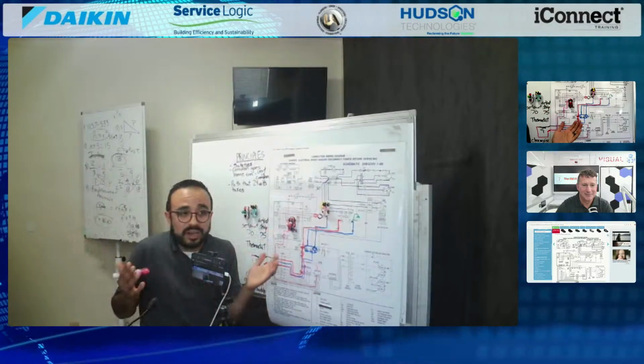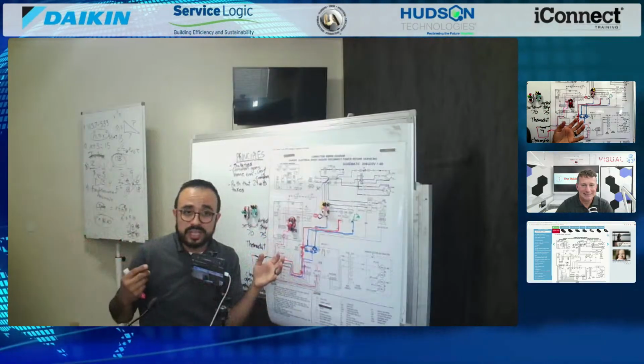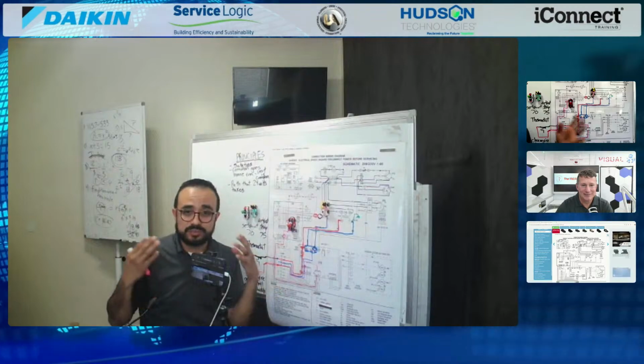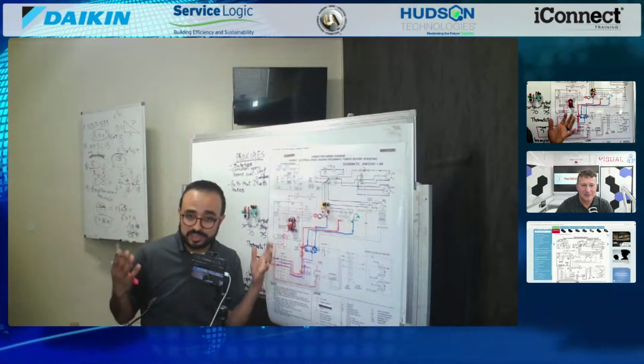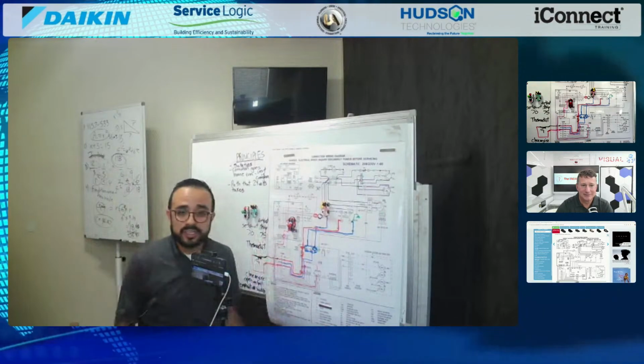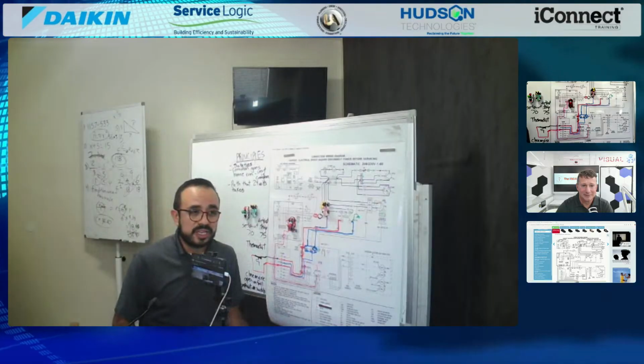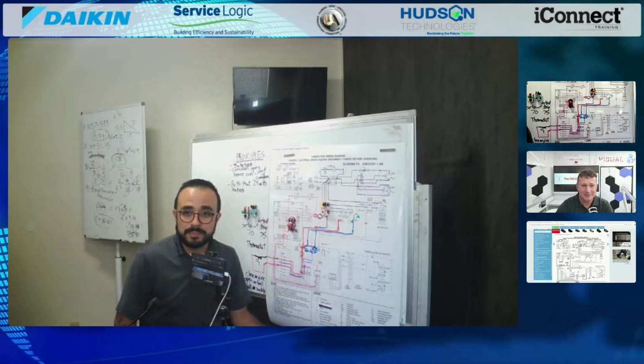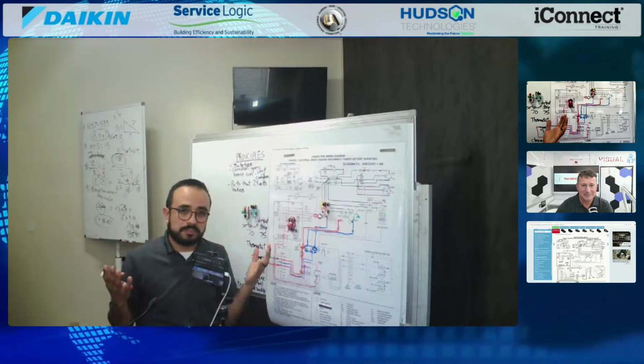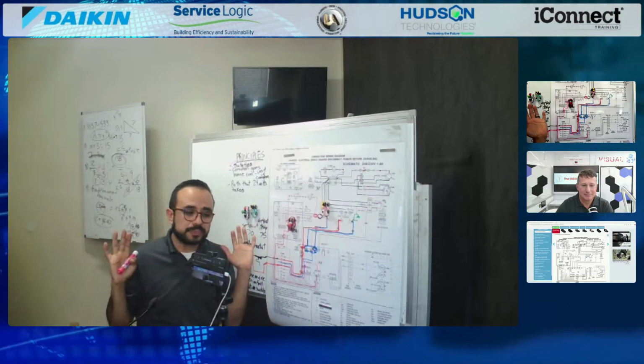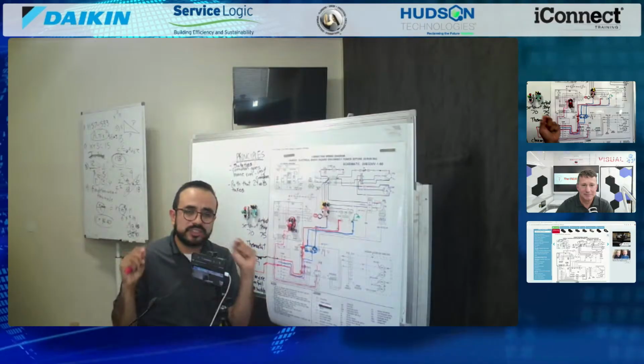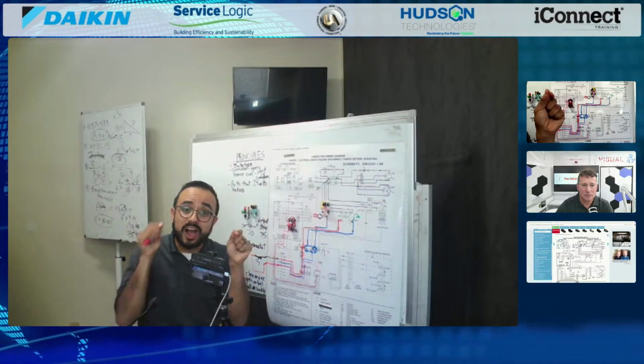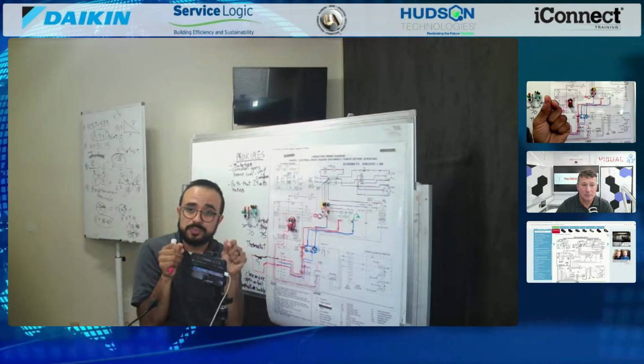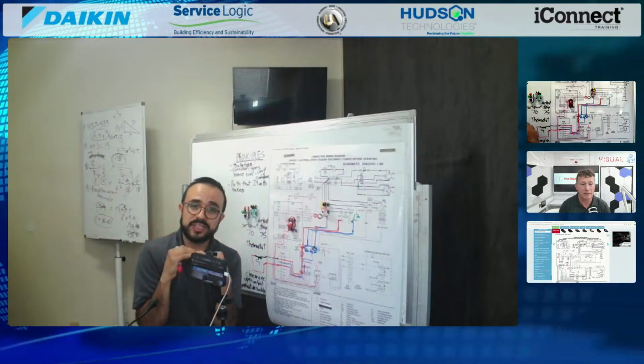And so, I have seen some systems that don't have safeties or pressure switches. That's really bad practice. It should have safeties, at least the low pressure switch, but they should have both pressure switches. But the concept is the same: power in, power out. And I do have a lot of students at times that send 24 volts in common to a safety switch, but it's just a switch, it's not a load.